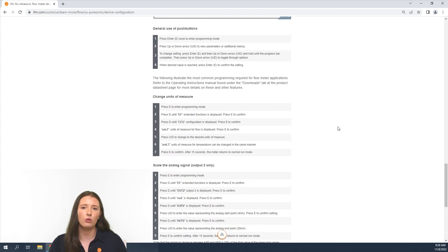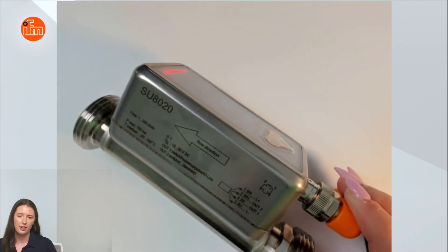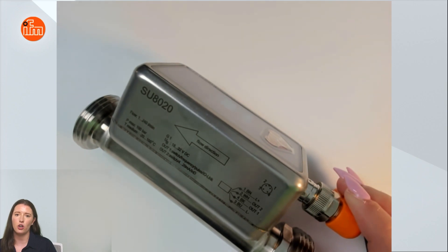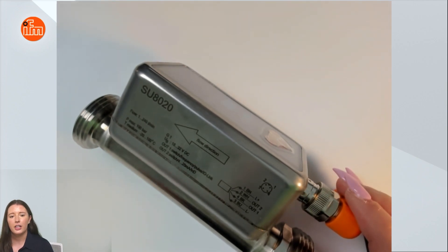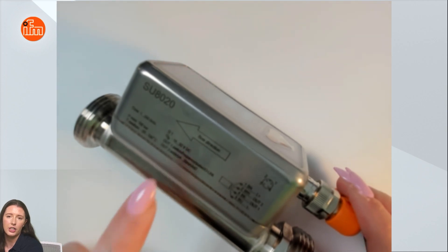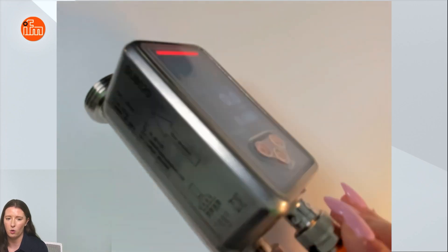Now let me take you to the SU device itself and show you how to use the installation wizard as well as change different parameters using the display and push buttons. Here we have the SU 8020. This specific part number has a G1 process connection. For other options with different process connections and sizes please check out the select products page on our Learn More site. Here you can see we have the flow direction arrow etched on the side of the sensor, and now let me show you the TFT display with the PFA window for chemical compatibility.